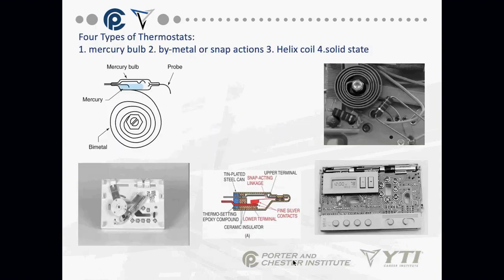Okay, there's basically four types of thermostats. We have the mercury bulb, we have what we call a bimetal snap action, we have a helix coil, and we have solid state. Okay, the mercury bulb is this one top left. As the bimetal coil expands and contracts when it gets hot or cold, the mercury bulb will start to move up and down, and these contacts here will become made or broken based on where that mercury is. Okay, it's actually an ingenious device for being close to 100 years old.